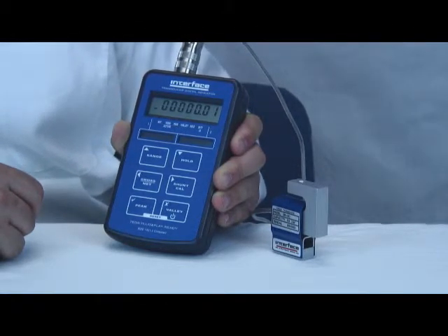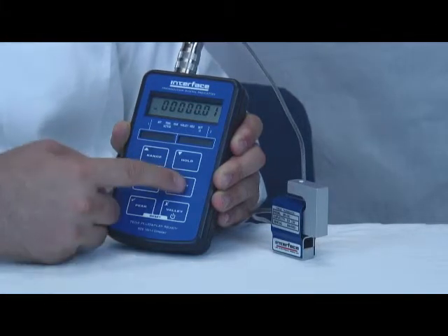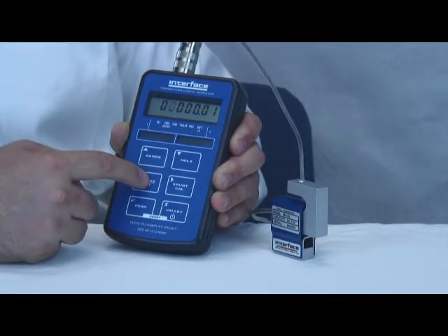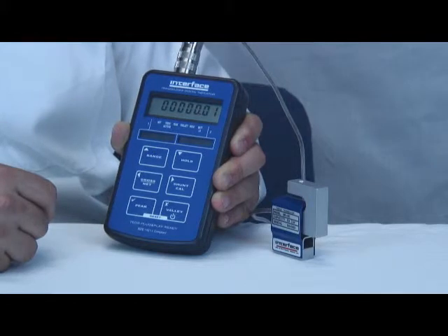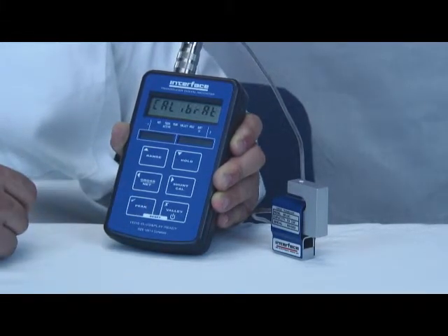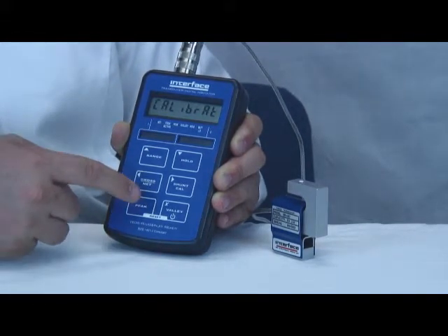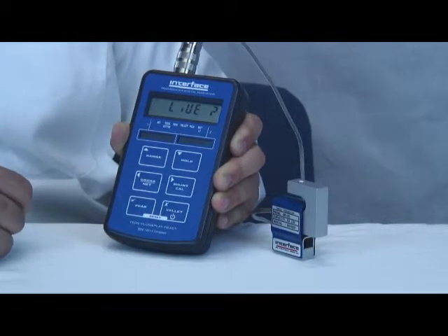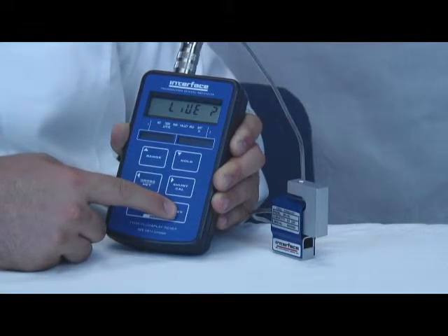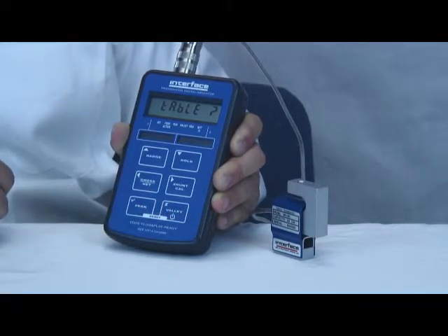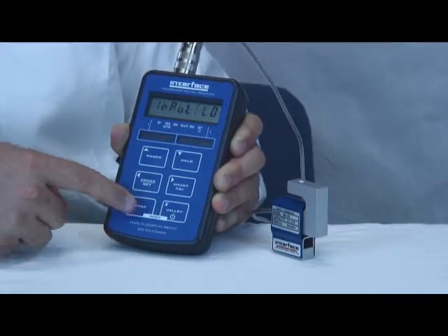You can see the resolution is already set, but if we wanted to change it, we would use the arrow buttons to change and then check to confirm. Calibrate, check to confirm. Now it asks if we want to do a live calibration with applied loads or not. We don't. So we're going to press X, and now it says, do you want to do a table calibration? This is where you enter a millivolt per volt value. So we say yes to confirm.